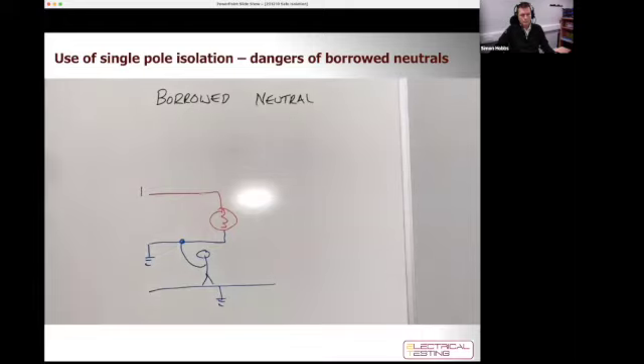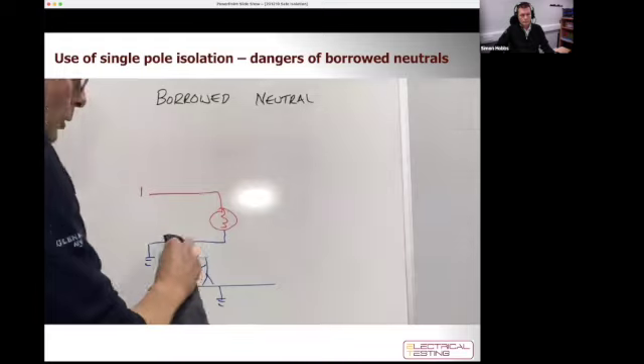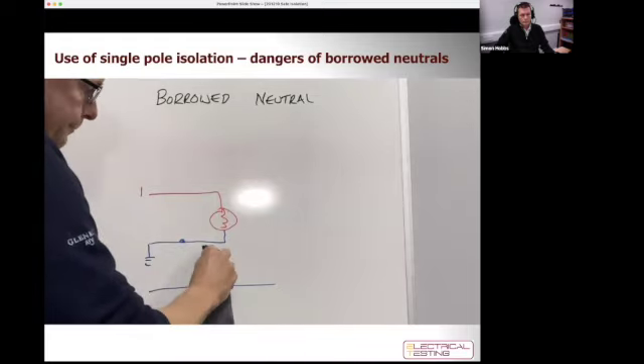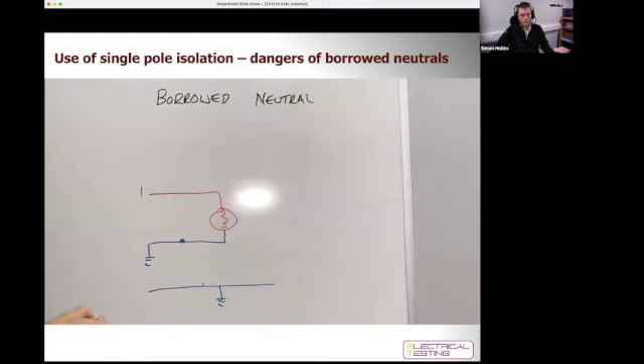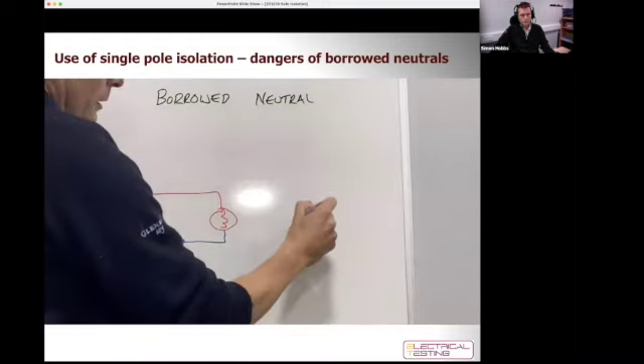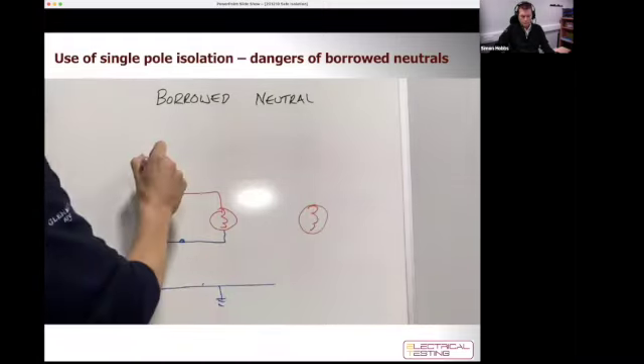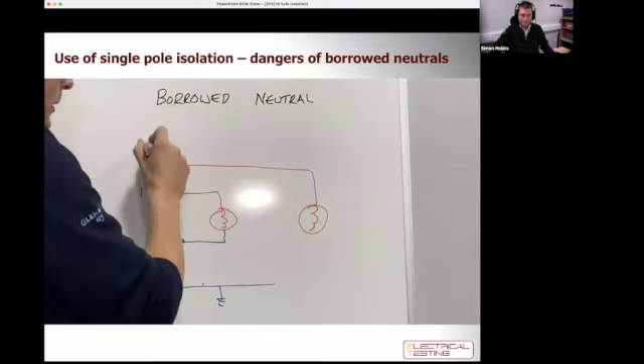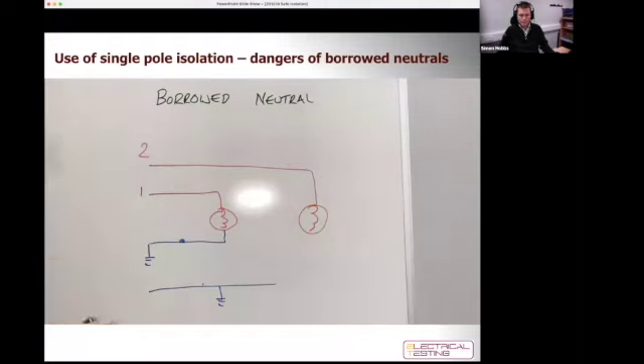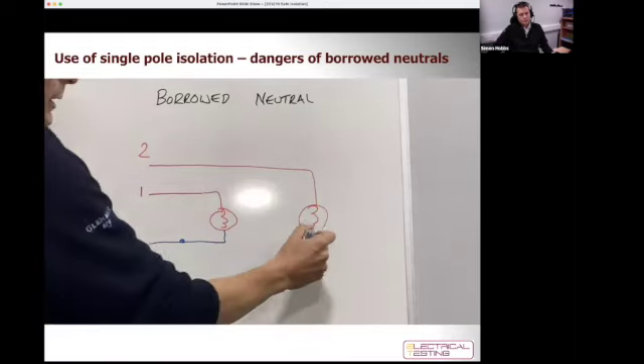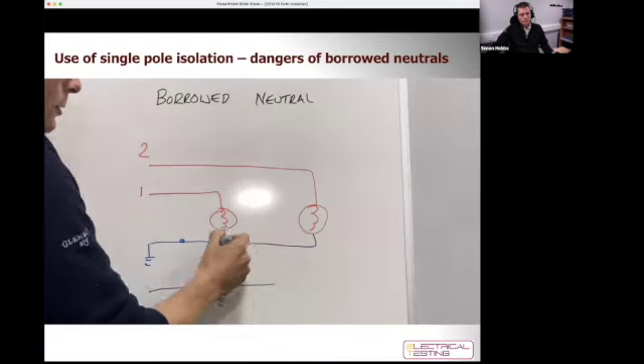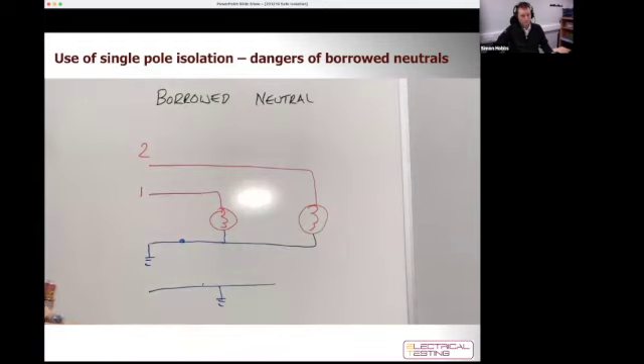So what is the problem with borrowed or shared neutrals? Well, the problem occurs when I want to put a second light in, and I create circuit 2. So there's my line conductor for circuit 2. And for other reasons that we'll discuss separately, we use the neutral that's already there for circuit 1, usually to do with a length issue and having to not run in additional cables and cheapness.